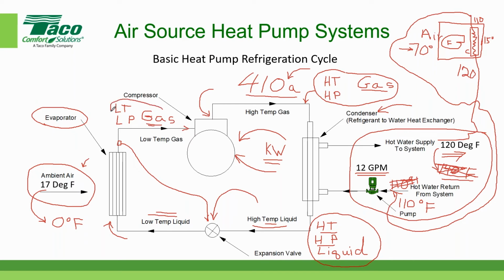There it goes. From a low temperature, low pressure gas, it goes through the compressor and becomes a high temperature, high pressure gas. And that completes the refrigerant cycle in its most basic form. There's a lot of stuff going on inside that box. But ultimately, we are extracting heat from air that's around 17 degrees Fahrenheit and generating hot water that's around 120 degrees Fahrenheit. And that's the magic of an air to water heat pump. Isn't that exciting stuff?